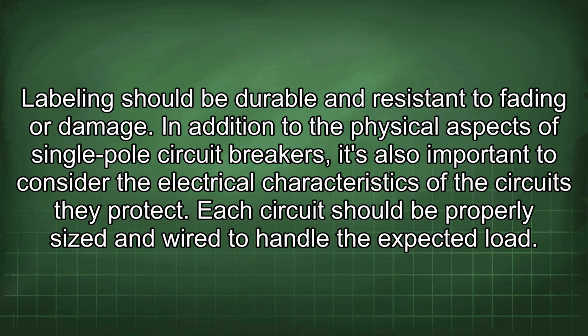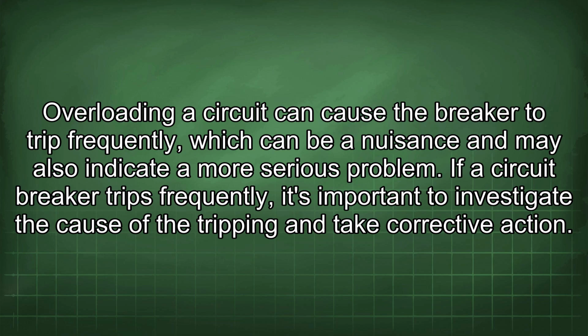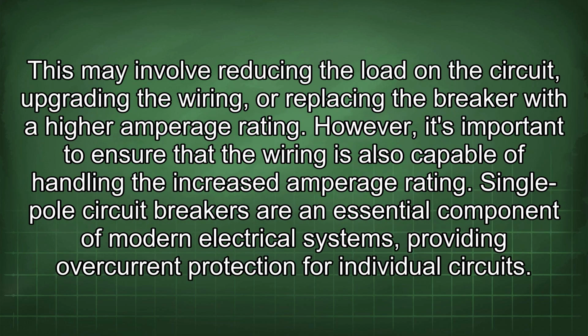In addition to the physical aspects of single-pole circuit breakers, it's also important to consider the electrical characteristics of the circuits they protect. Each circuit should be properly sized and wired to handle the expected load. Overloading a circuit can cause the breaker to trip frequently, which can be a nuisance and may also indicate a more serious problem. If a circuit breaker trips frequently, it's important to investigate the cause of the tripping and take corrective action. This may involve reducing the load on the circuit, upgrading the wiring, or replacing the breaker with a higher amperage rating. However, it's important to ensure that the wiring is also capable of handling the increased amperage rating.